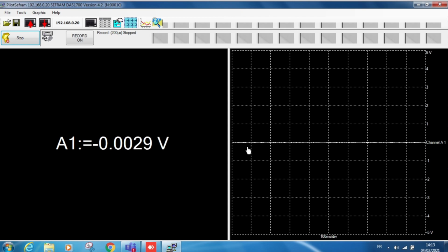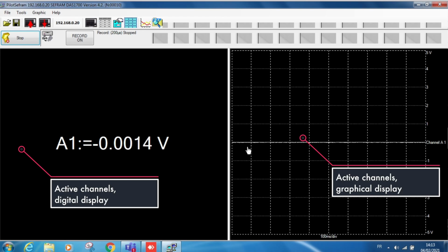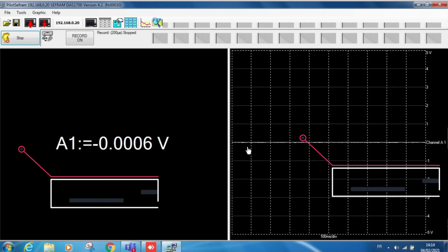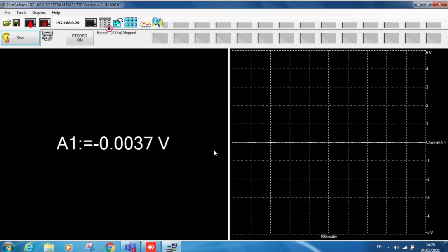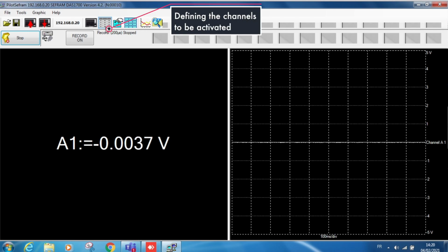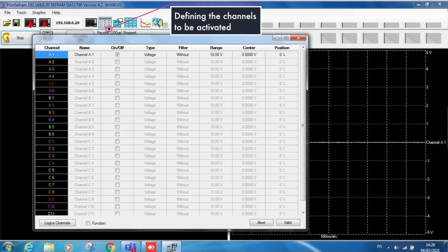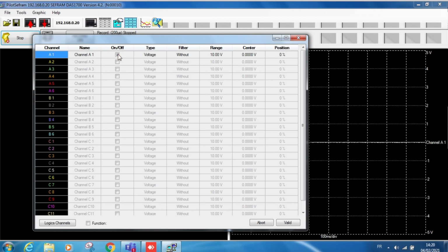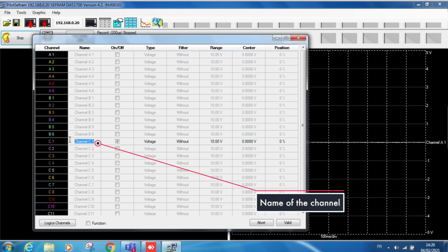The device is now in remote control mode, which means it's the computer that controls the instrument. You can visualize the active channels on the instrument, both graphically and numerically. Let's first define the channels we want to enable and disable. In our case, we will disable A1 and enable C1. Our C1 channel is an ambient temperature recording.